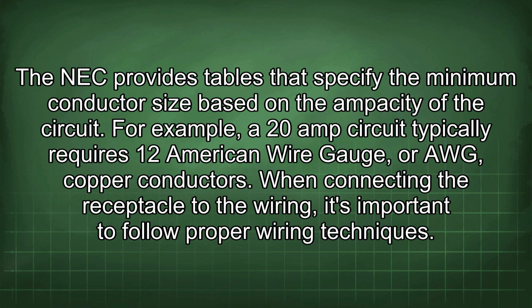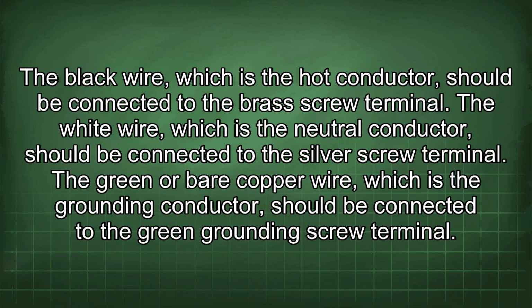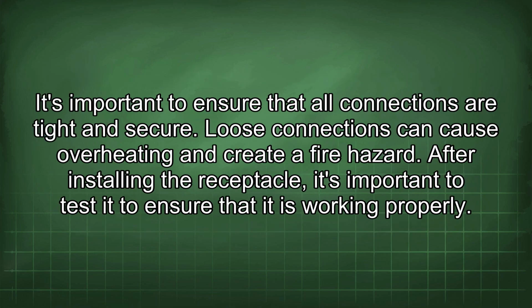When connecting the receptacle to the wiring, it's important to follow proper wiring techniques. The black wire, which is the hot conductor, should be connected to the brass screw terminal. The white wire, which is the neutral conductor, should be connected to the silver screw terminal. The green or bare copper wire, which is the grounding conductor, should be connected to the green grounding screw terminal. It's important to ensure that all connections are tight and secure. Loose connections can cause overheating and create a fire hazard.